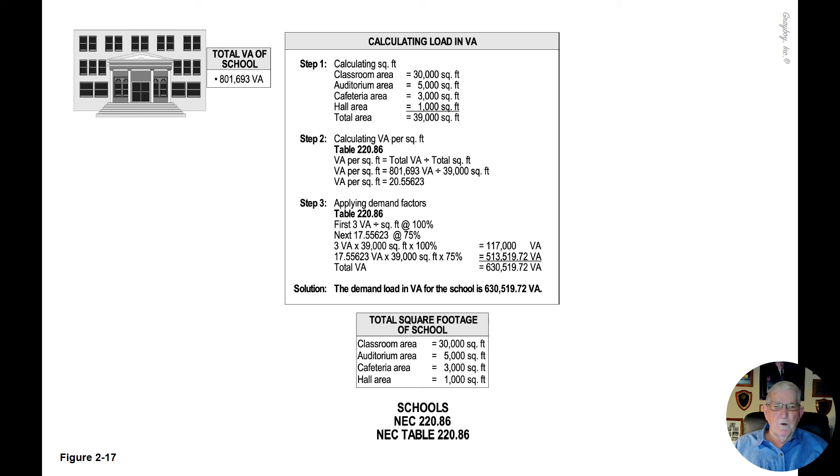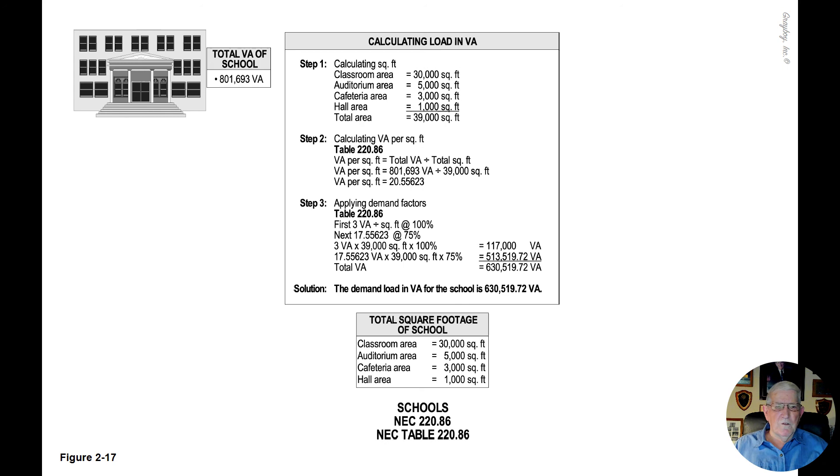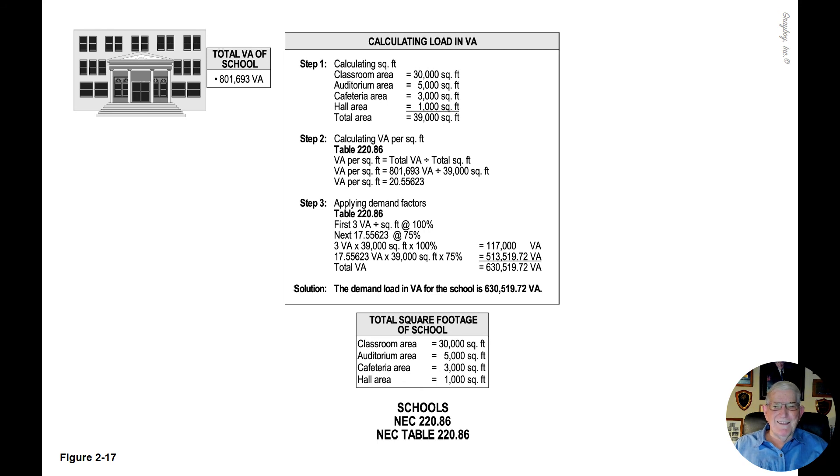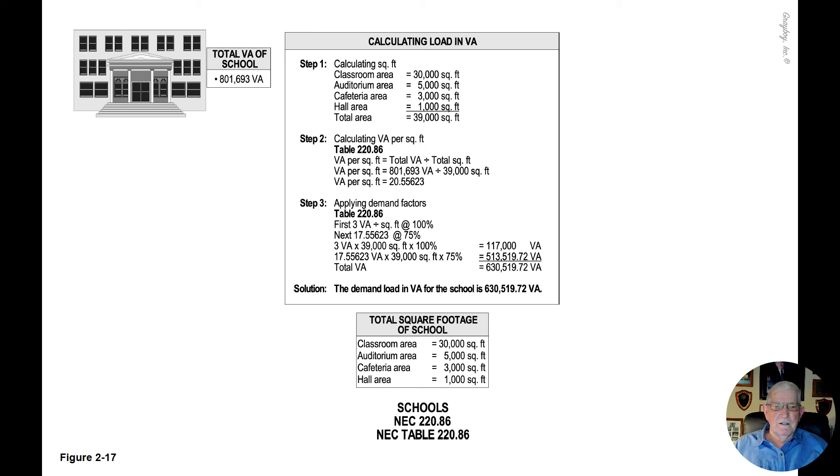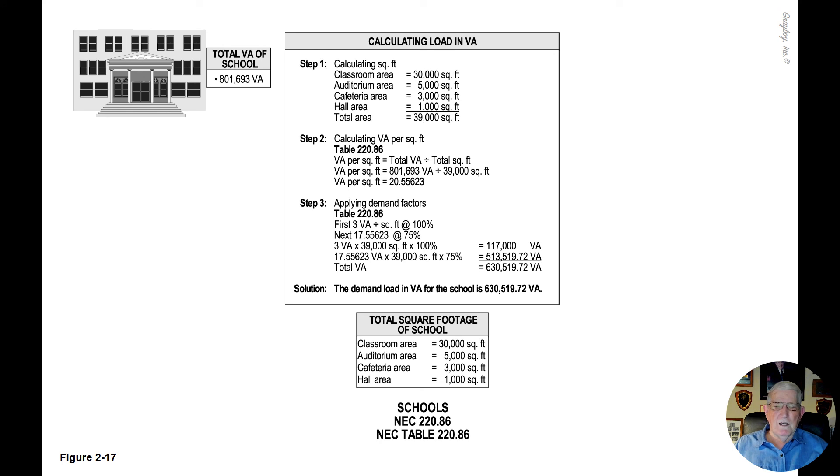When the math is completed, we come up with a total VA of 630,519.72 VA. So the demand load and the answer, the demand load in VA for this school using the optional calculation with demand is 630,519.72 VA. And that's what this figure 2-17 is illustrating.